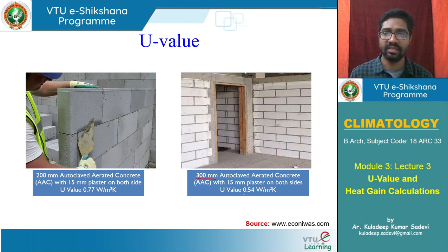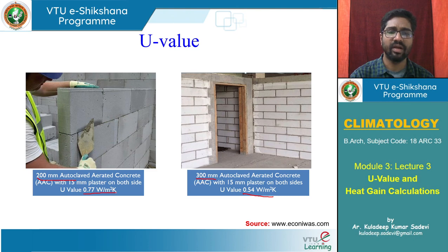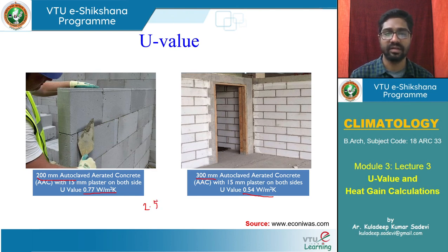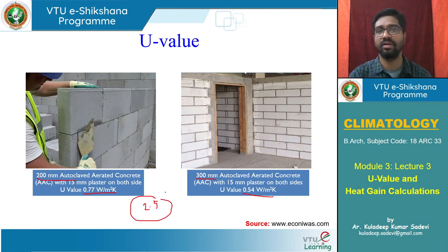The 300 mm AAC block wall has 0.54 W/m²·K, whereas the 200 mm AAC block wall has 0.77 W/m²·K. A 9-inch brick wall is roughly about 2.5 W/m²·K. These are rough numbers to understand the thermal resistance or thermal transmittance values of these walls.